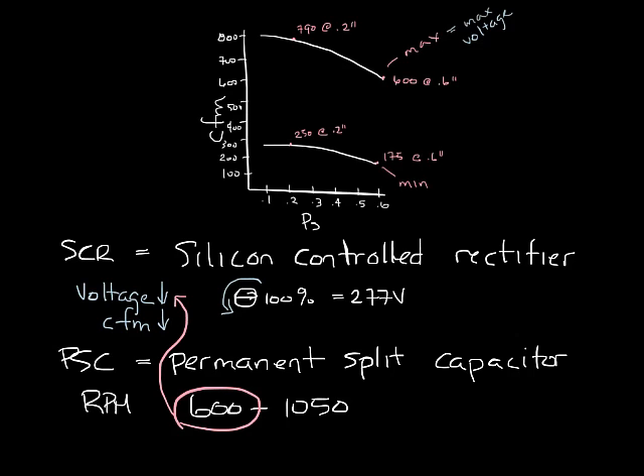So as you turn the SCR down you need to stay above the minimum RPM for the motor as well. The way fan box manufacturers do this is by setting a minimum turn down on the SCR. This is based on the manufacturer's fan box testing to ensure that over normal operation pressures the SCR keeps within its operating range. So back to the minimum fan curve line. The minimum fan curve represents the airflow when the SCR is at minimum or the line where you stay above 600 RPM.